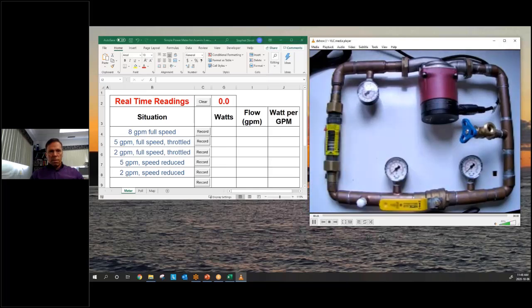So what I'm going to do first of all is run this pump through its paces. I've got a little pump here, which actually has an ECM motor in the pump, and it has a number of different settings, but I'm going to use the fixed speed settings on it. It does have an adaptive mode. Most manufacturers have a pump of this size that does this, but I'm not going to use that particular mode. I'm simply going to set it to full speed, which is what I'll do right now. Okay, and that pump is now running in full speed mode.